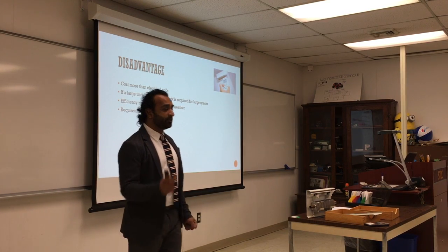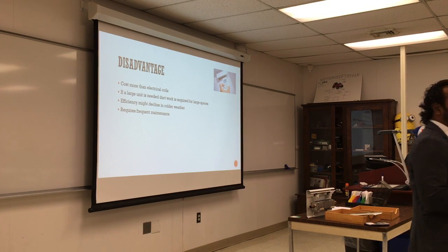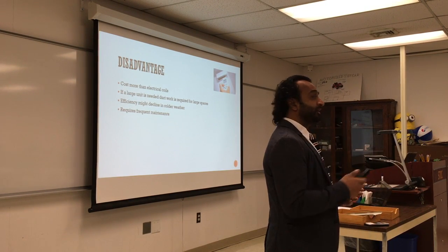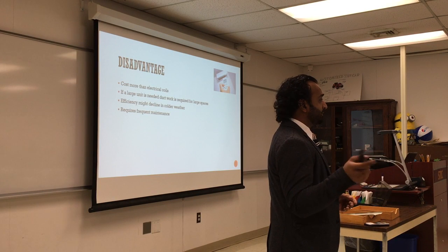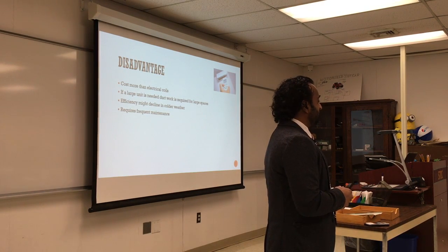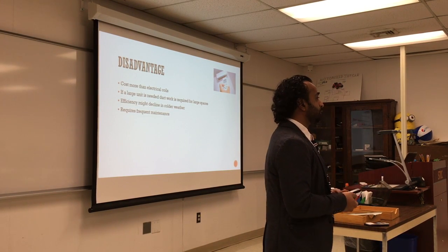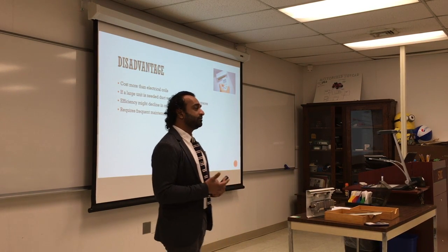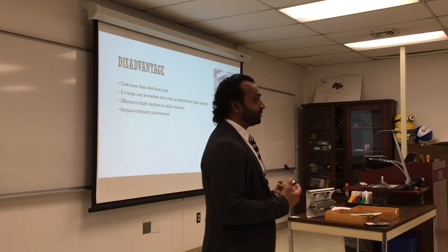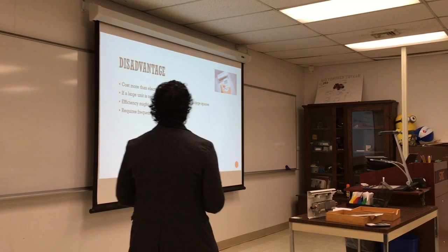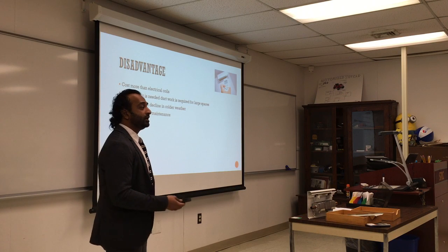Requires frequent maintenance. With minisplits, probably you're gonna have somebody come from Bill Pumps and give you a small course about Fujitsu installation. And they will tell you those require a lot of maintenance. You have to clean the indoor unit frequently and the outside. And the filters have to be washed at least once a month, which is very inconvenient because look at the location. You're gonna bring a ladder and go and take it and wash it. And the compressors for these units are very, very delicate. So if you have any kind of leaks and you don't monitor that leak, it will overwork and eventually it will break. So they require frequent maintenance, and if you don't do the maintenance as suggested, that will void the warranty.